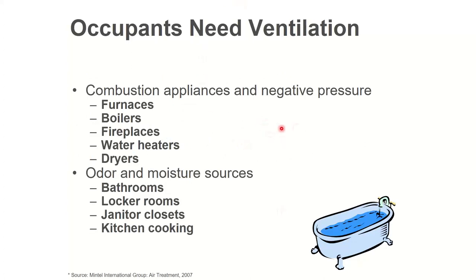There are other reasons why we need air coming into a building. And I don't want you to confuse combustion air with the fresh air we're talking about today. Your combustion appliances, whether it's a house or an office building or a restaurant, all those appliances need combustion air. The air I'm talking about right now is above and beyond that. I need fresh air for the occupants in addition to all the CFM I need for the combustion. So whatever this boiler has for exhaust, let's just say it's exhausting 300 CFM, somewhere 300 CFM has to come in to make up the 300 going out. So I got to have all this combustion air coming in.